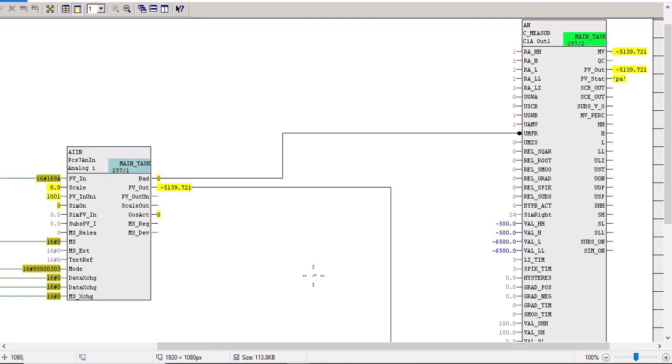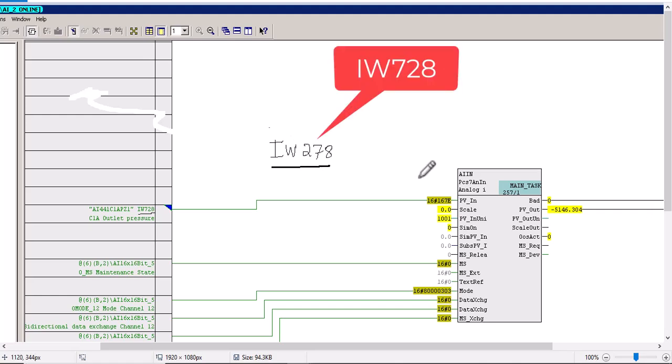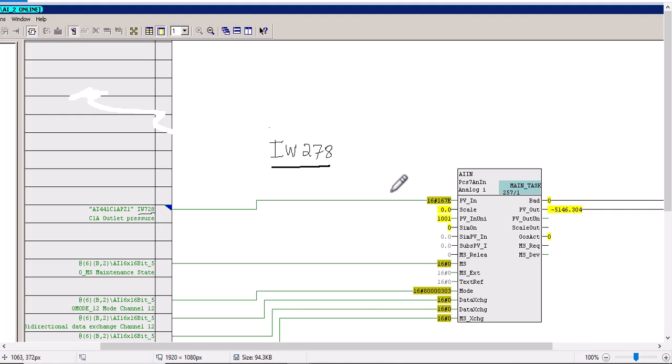Let me show you how the analog values have been interfaced with the CMART block. As you can see, IW728 — just ignore this PCS7 analog input block for now. All you need to know is that the PV_In input has been connected with IW728. 728 is the address of the analog input channel of this particular PLC — in this case an S7-400 — and the pressure sensor is interfaced with this particular channel.